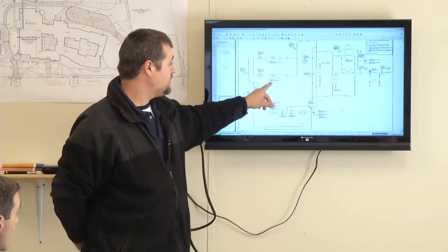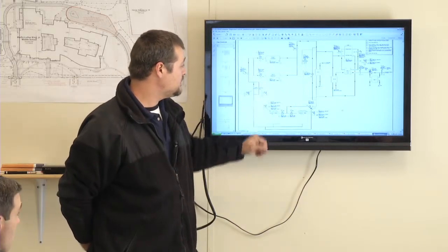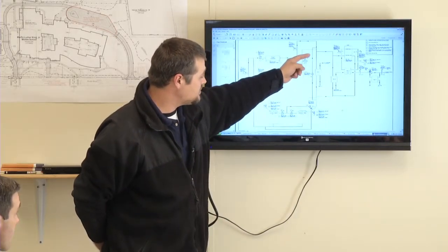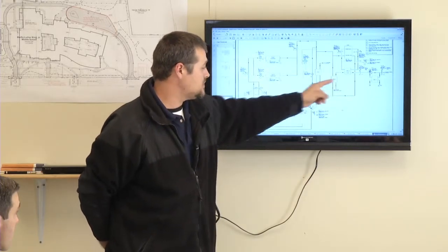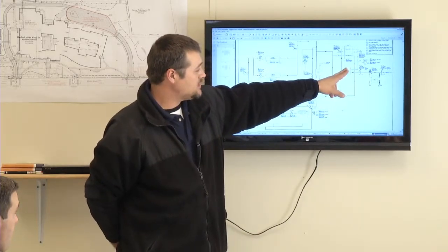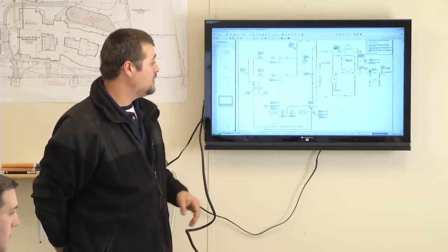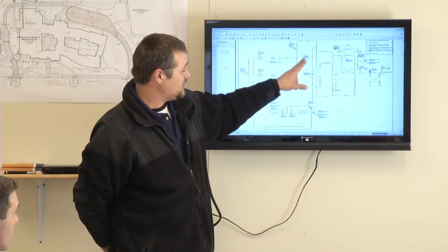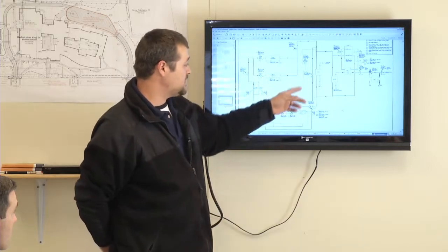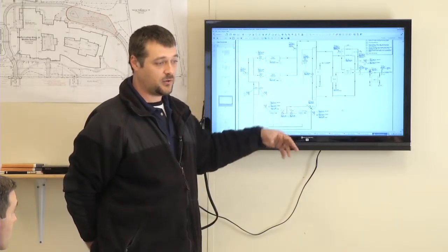We have a discharge temperature on the other side labeled CRT. This is condenser return, but it's the discharge through the barrel after the chillers warm the water back up. And then we have a differential pressure sensor measuring the DP across the heat exchanger section here. This is a two-way bypass valve. If our energy recovery machine is operating, which if the chiller is operating, it calls for in the sequence to run that machine, then we'll divert some of the water from the cooling tower into that heat recovery machine, allowing the flow switches to make. This will be set by the balancer on whatever flow requirements it takes to make that unit run.